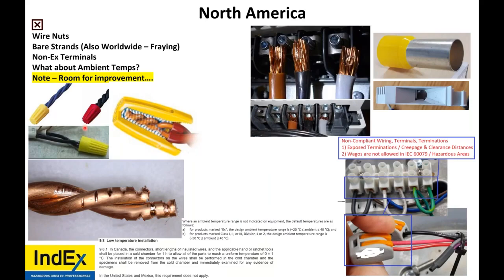But what's the problem with wire nuts? They damage, well, your wires. So if it's your connection means and you're using a wire nut, is the wire nut EX rated? You know, all terminals need to be EX rated inside of EXE. So if you're to use a wire nut inside of EXE, please, somebody tell me where an EXE wire nut exists. It does not. So it actually calls into, for low temperature, there's low temperature tests to be done. These terminations will not pass.